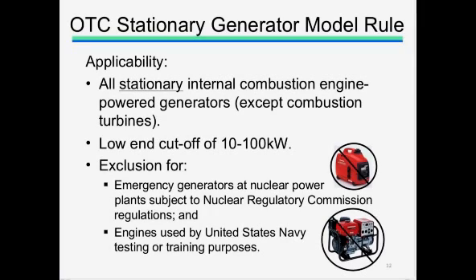The model rule initially began as an update to the Ozone Transport Commission's model rule for additional NOx control measures, but it was tailored to specifically apply to stationary generators powered by internal combustion engines, and it specifically exempts combustion turbines from its requirements. The model rule includes a low-end cutoff between 10 and 100 kilowatts, which states may decide at their discretion, but it does not include a high-end cutoff. Based upon stakeholder comments and review, the model rule does also include exclusions for emergency generators used at nuclear power plants subject to Nuclear Regulatory Commission regulations, as well as engines used by the United States Navy for testing or training purposes.